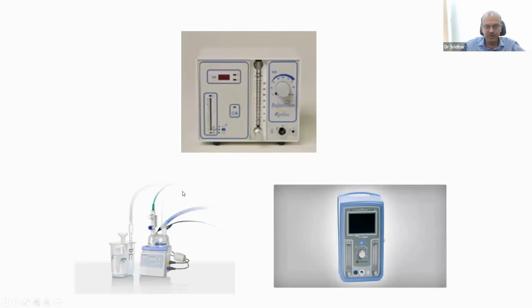There are many devices used to provide CPAP as well. So you can see here the infant flow driver, the CPAP machine, and biphasic CPAP is delivered through this one. As I mentioned, there are many other brands which come up with the biphasic CPAP model. The flow driver, we have the Aladdin, we have the Fabian one, we have Medin. So different companies are coming out with similar devices, and all of these work through a flow generator at the nasal level. Infant flow driver we call it, and the SLE CPAP, the single limb one, also uses the same mechanism.